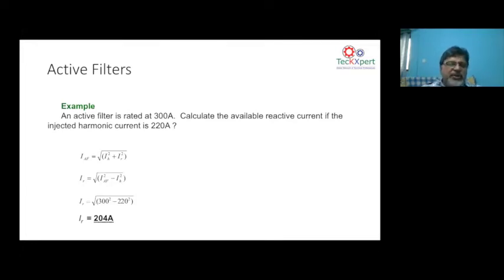For example, 204 amps, if you multiply by 1.732 into 0.4, it could be somewhere about 100 plus kVAR. That means this can give you around 130, 140 kVAR of reactive power compensation and 220 ampere of harmonic mitigation. So a properly selected active harmonic filter is more than enough instead of going for a capacitor bank. Go to the next.